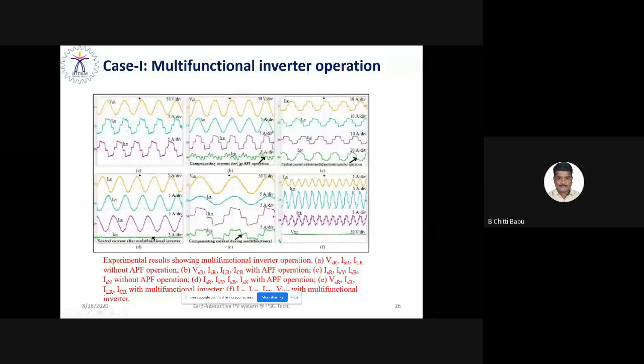So now the grid-connected, shunt-connected voltage source inverter injects a complementary component of the harmonics present in the supply current, so that it compensates the harmonic component and your supply current is sinusoidal. Still you are connecting a three-phase non-linear diode rectifier load, but the supply current becomes sinusoidal. This is possible with the help of the shunt active power filter. Now see figure C, without the active power filter. Without it, your supply current for each phase is a staircase, a stepped wave.